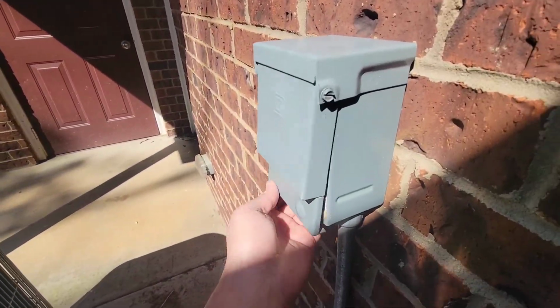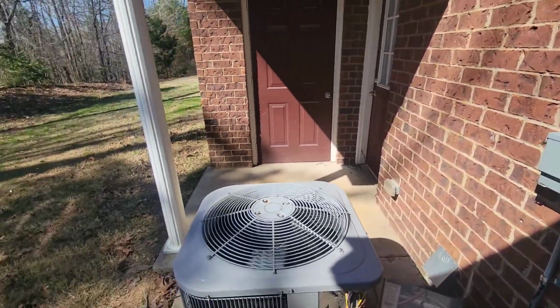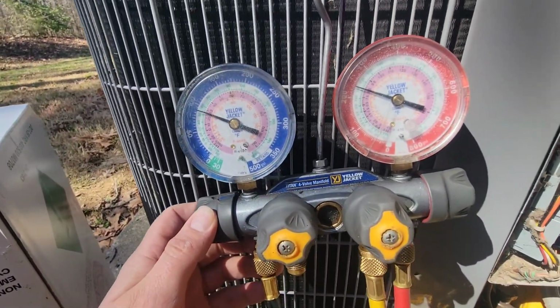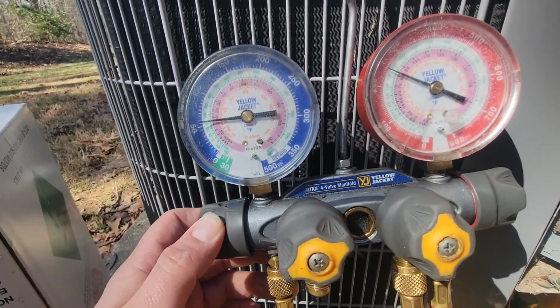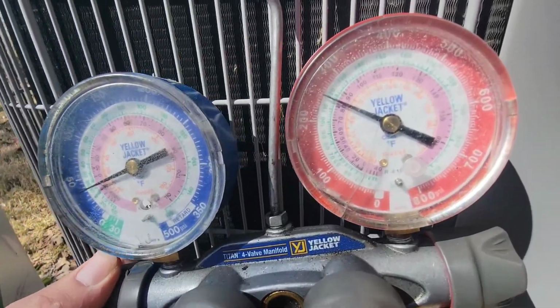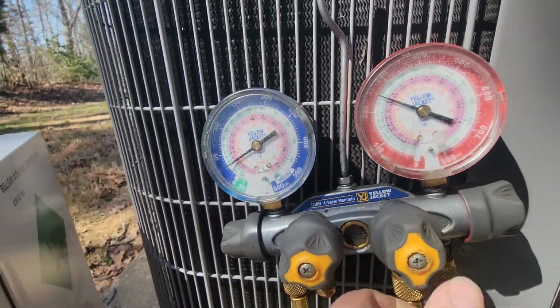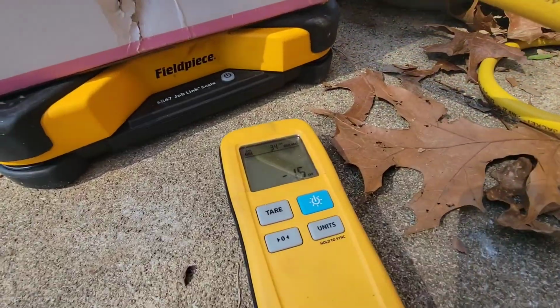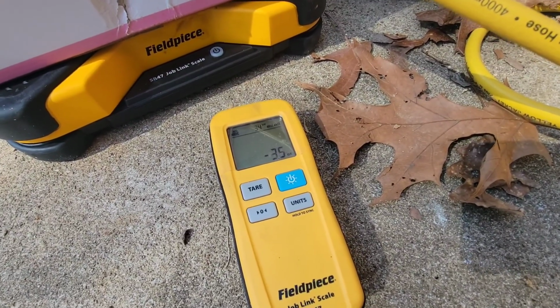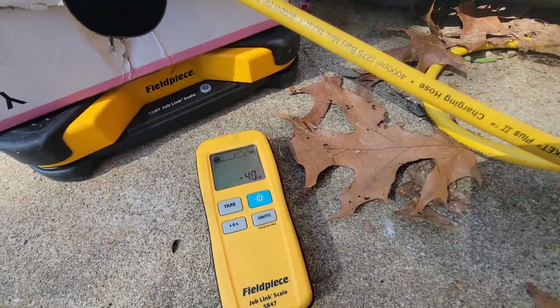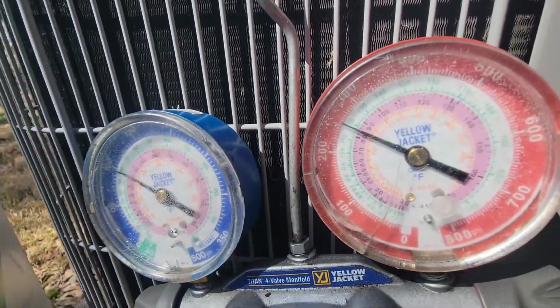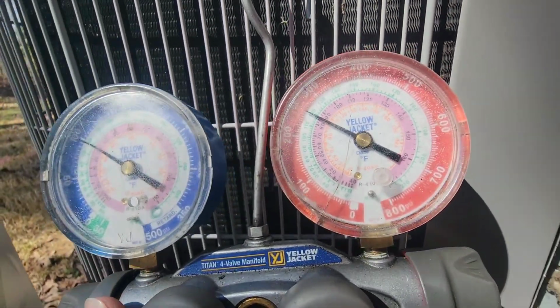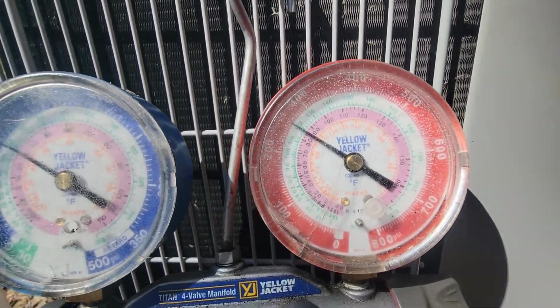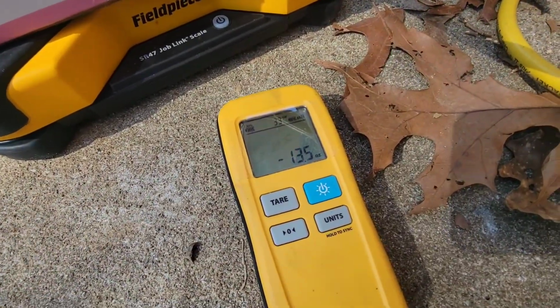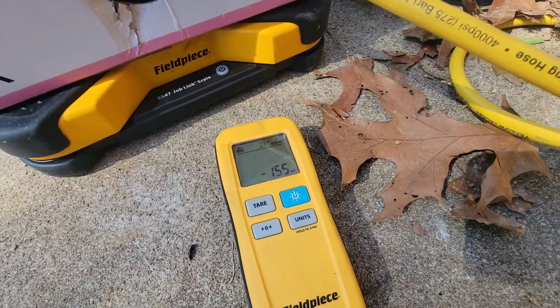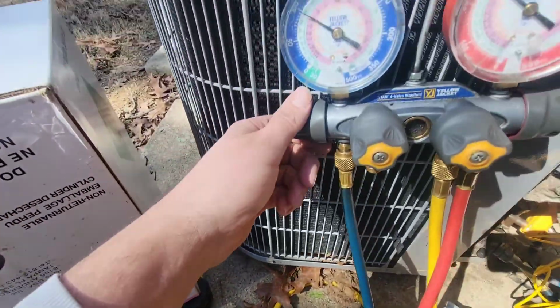Okay. Let's turn it on. Let's add some refrigerant. 250 on the high side. All right, we'll go ahead and start adding. You see we're adding 4 ounces. Pressure on the high side, slowly going up. Got 13 ounces, almost a pound. 16 ounces makes a pound. There's 16 ounces, that's 1 pound. We're gonna turn it off.